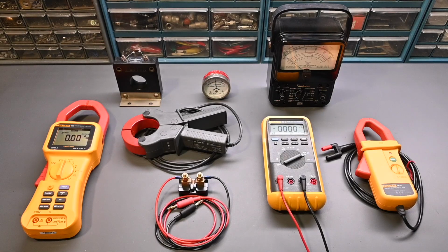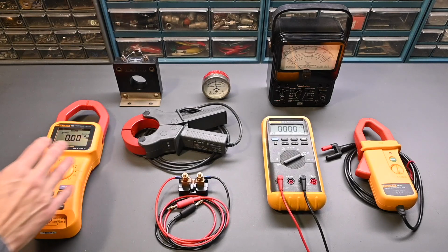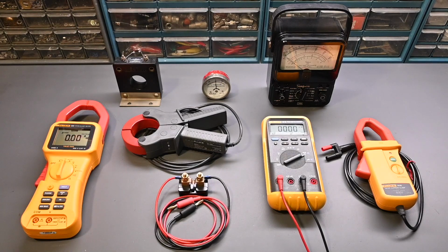Then the second way is that you can inductively sense the current flow, using the fact that a current-carrying conductor produces circular magnetic fields around it. So of course, the higher the current flow, the stronger the magnetic field. That's exactly how something like a clamp meter is able to detect current flow. So let's take a look at the 5 ways that you can measure current based on these two principles and some pros and cons of each.